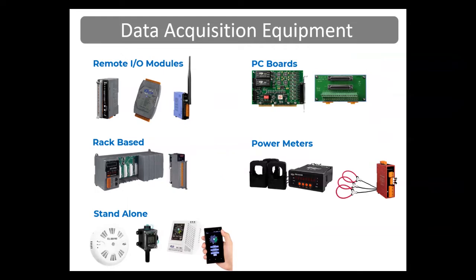Our remote I/O modules are communicable over different protocols including Modbus RTU, Modbus TCP, BACnet, CAN open, DeviceNet, Ethernet IP, EtherCAT, MQTT, and Profinet. Protocols are like languages that devices can communicate in, each with their own rules, syntax, synchronization, and error recovery methods. Modbus is one of the most commonly used protocols — it's a simple, standard, and robust serial-based communications protocol used for industrial communications for instrumentation, control, and data acquisition. It was originally published in 1979 by Modicon for use with its PLCs. Many software applications support Modbus, including SCADA software, LabVIEW, DASYLab, Visual Basic, and C language.